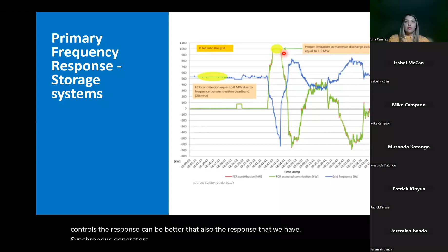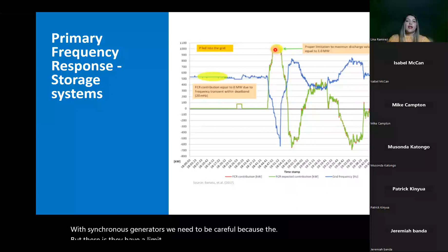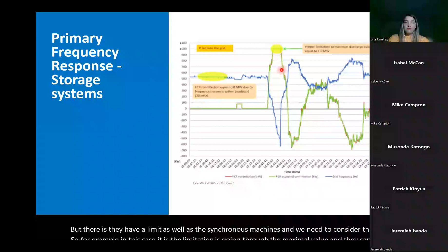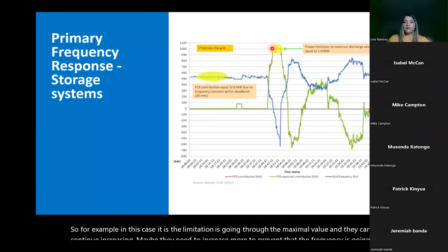And we start to see that, as I mentioned before, since it is based on controls, if we tune the controls really well, the response can be better than the response that we have with synchronous generators. We need to be careful because batteries have a limit, as do synchronous machines, and we need to consider that. In this case, the limitation is the maximal value and they cannot continue increasing. Maybe they need to increase more to prevent the frequency from going down, but they don't have more energy, so they saturate and cannot provide more because they reach the current limit.